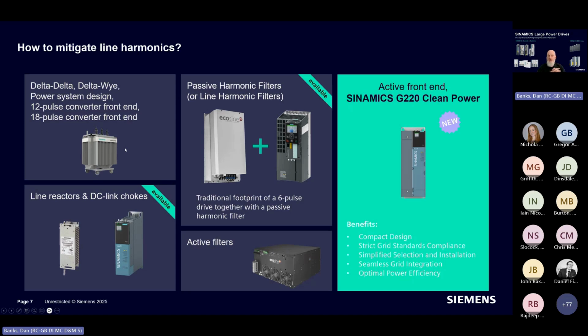You've got to have a transformer sat in front of your system to do that, to phase shift your supply, to turn your 3 phase into 6 phases or 9 phases or 12 phases. And you're putting those transformers in there, inherently inefficient. They're eating your power, they're generating heat. They're not where we want to be, and they're also expensive. You probably need to do maintenance on them, etc., etc.